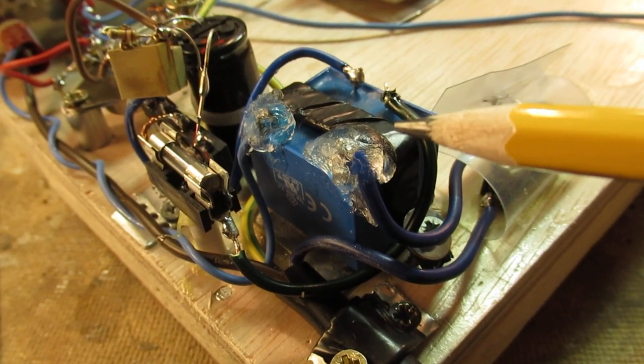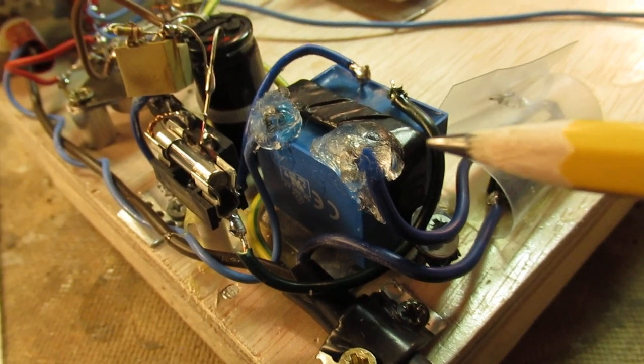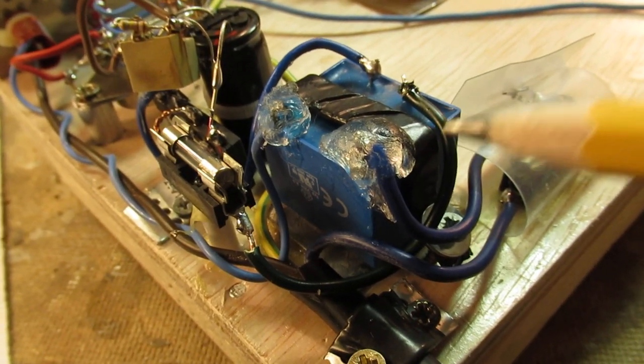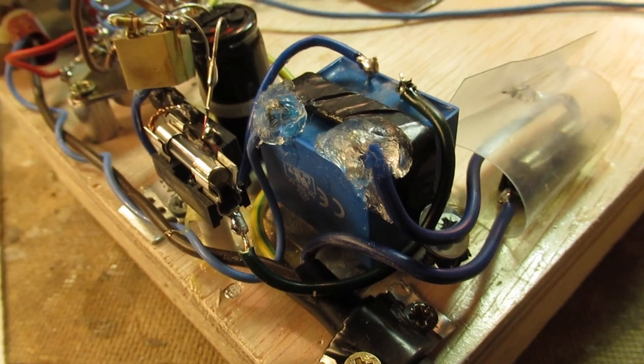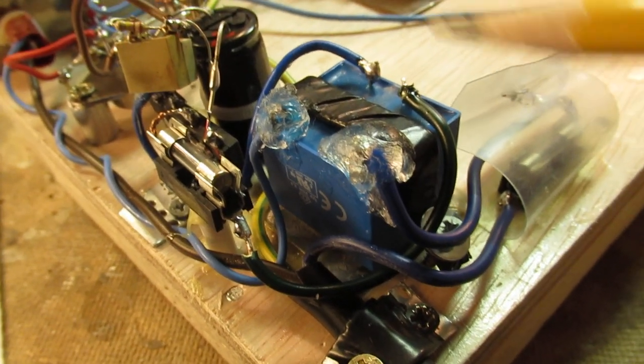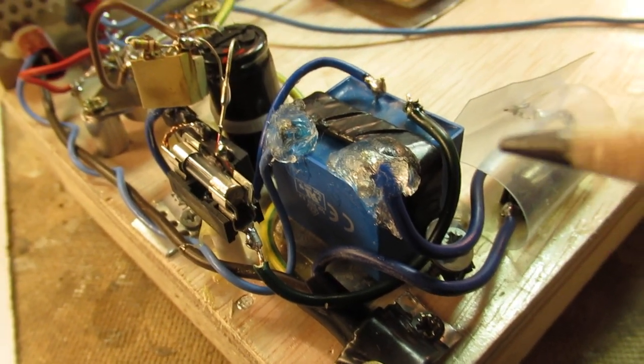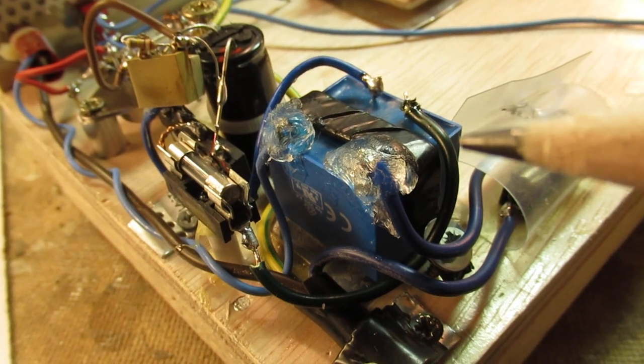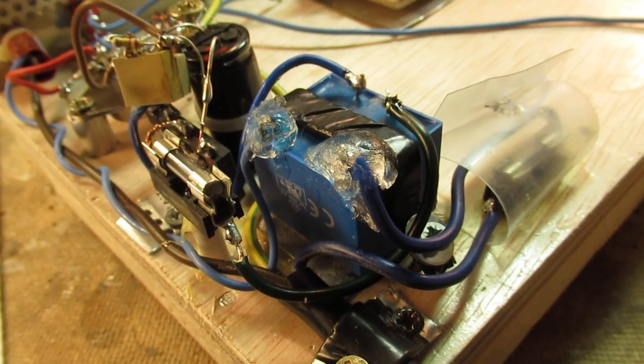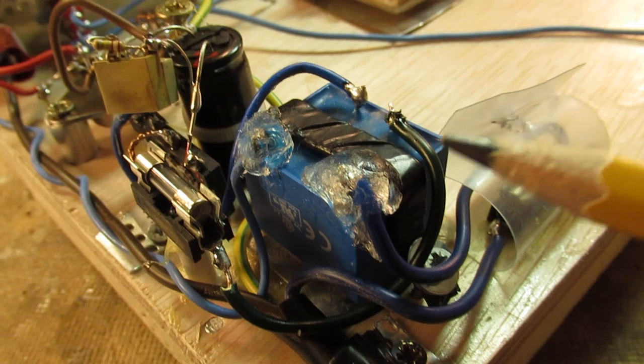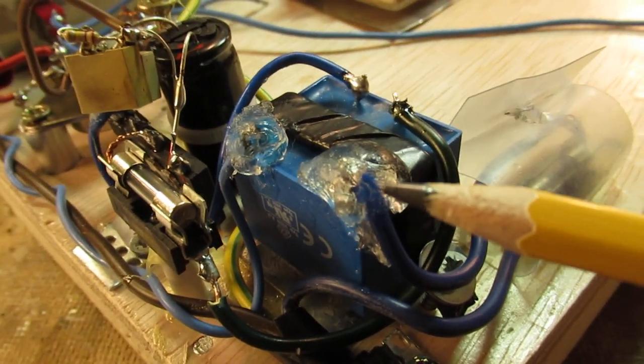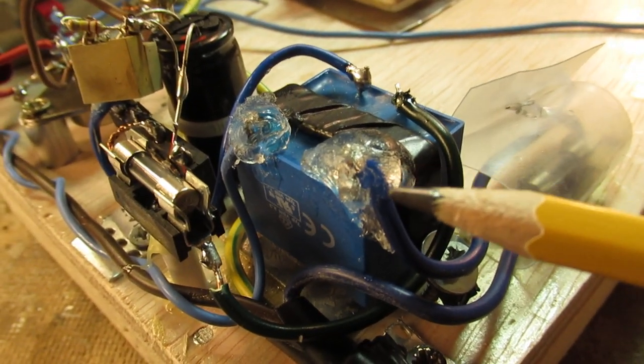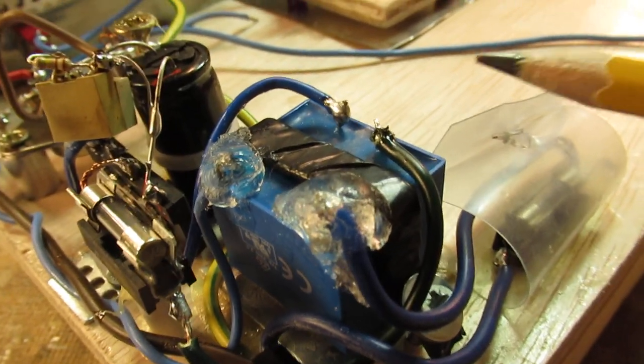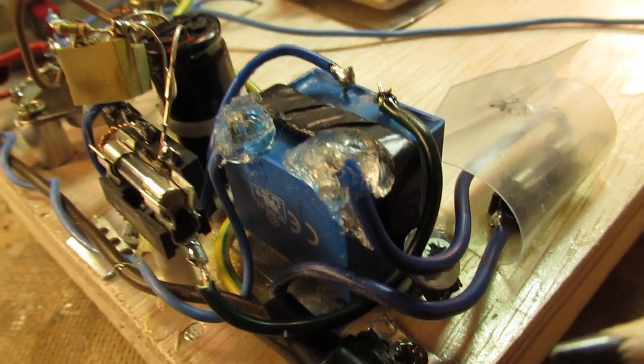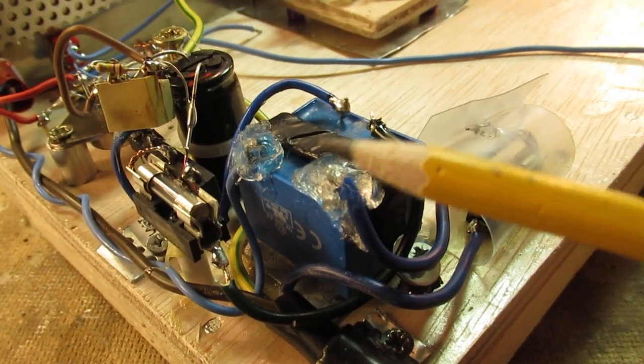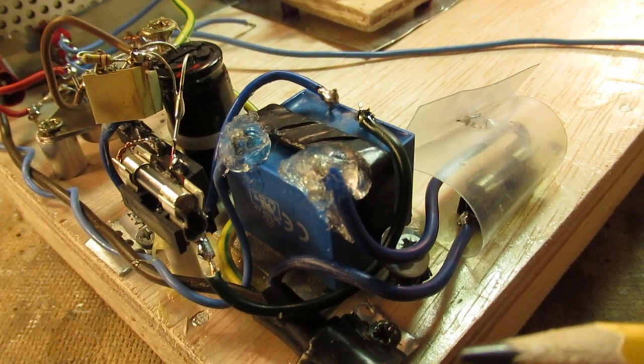That inrush current occurs in many cases because the transformer, in that first split second, is not in a state where it is able to give back energy to the primary circuit. That means the AC resistance in that first split second, when you switch on such a transformer with a load here, the inrush current can be very high.